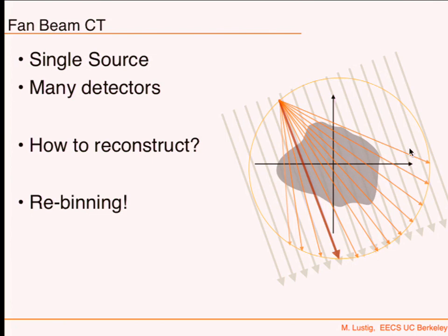Now, the more slices you have, there are other issues that I haven't talked about, which you'd cover if you take a medical imaging class. When you shine X-rays from here, this could be scattered, and that creates photons that are detected by this detector. And so the scattering adds a kind of noise interference. That could be a problem when you have all these arrays of detectors. That increases the scattering. So that's something they have to deal with.